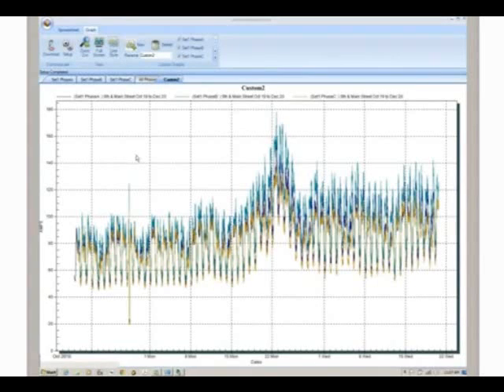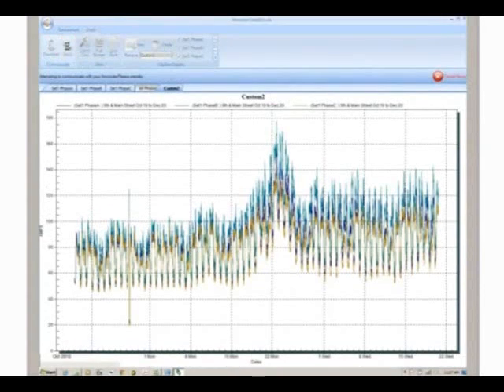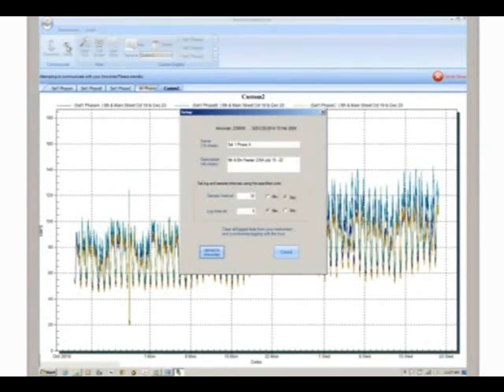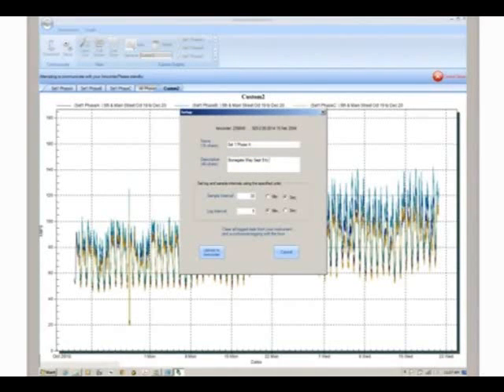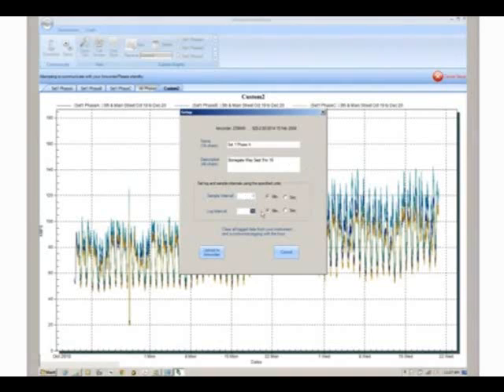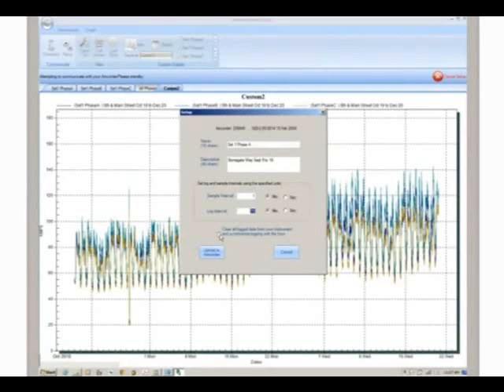Before redeploying your recorders, you may want to change their setup parameters. To do this, select the setup icon from the toolbar. Here you can change the name and description of the recorder. You can also set the sample interval to determine how often the recorder samples the line and the log interval to determine how often the recorder stores the average of the samples.